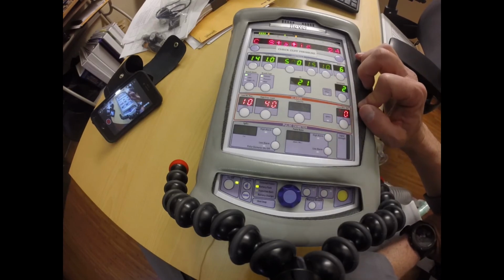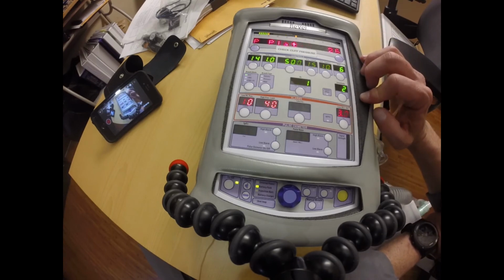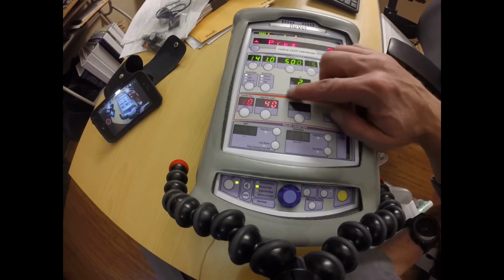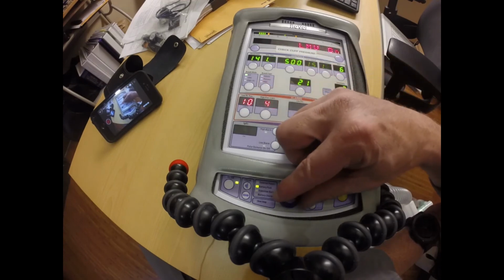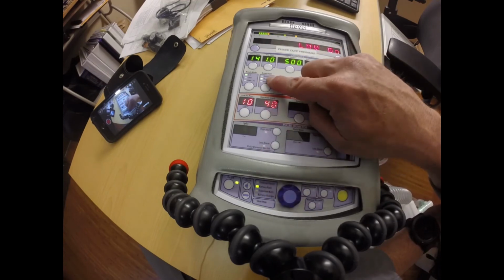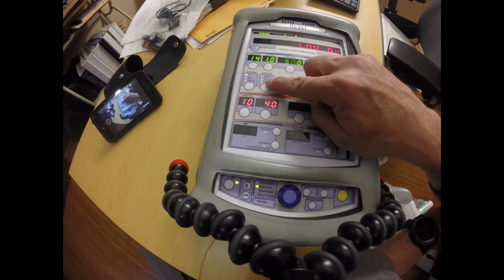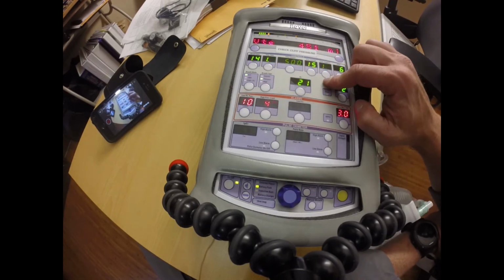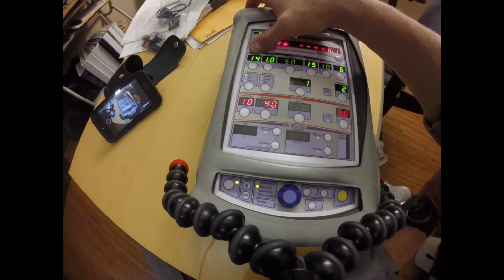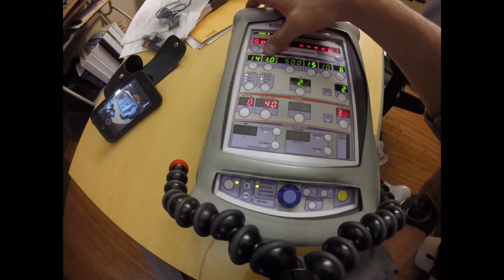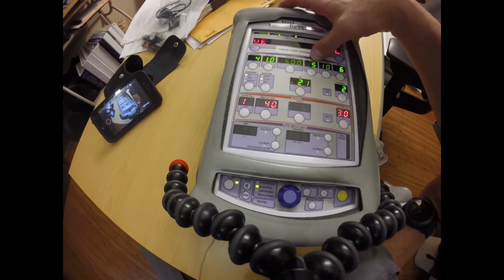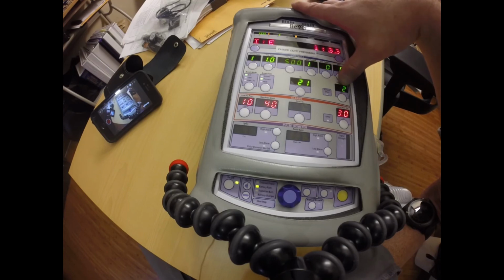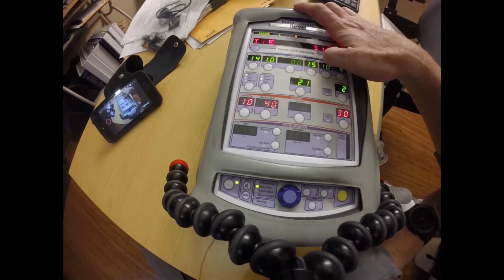If I want to go ahead and see what my auto PEEP is, then I'm going to move it over into a pressure control mode of ventilation. So again, it's blinking right there. If I don't push it again and lock it in, then it's going to go back to volume, but I'm going to choose to use pressure control. And you'll see right now that I'm at a breath rate of 14, an I time of 1, a pressure control of 15, with a PEEP of 6, sensitivity 2, and 21%.